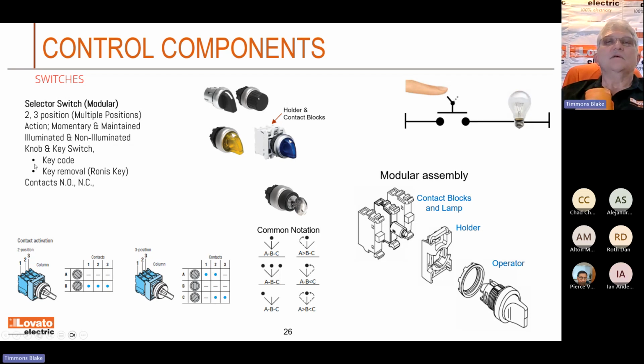Here we go. Selector switches work kind of like the push button, but you get a little more control. And there's usually a little truth table down here at the bottom. When I turn that switch to position 1, or position A or position B, which set of contacts get closed, or opened, or actuated, I should say? Three positions, you can kind of see how that works. The middle position will always be on for hours.